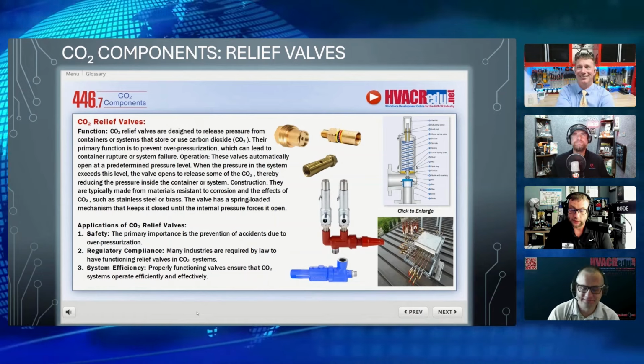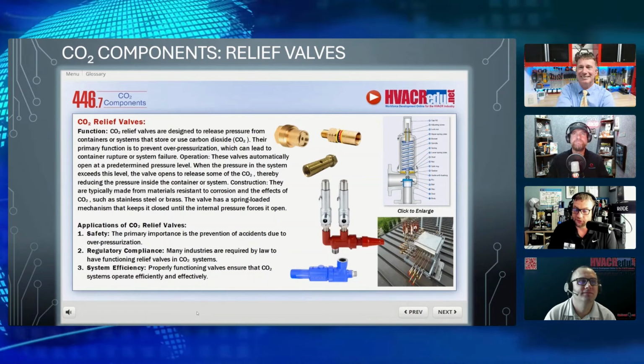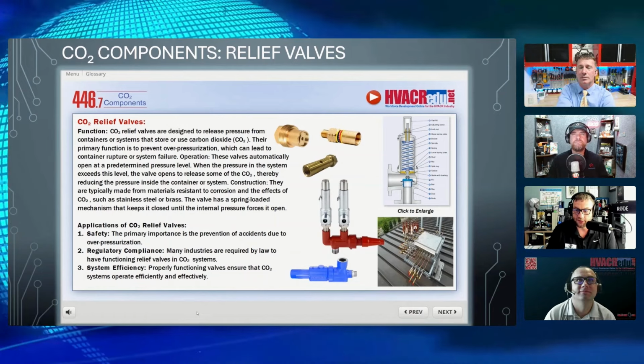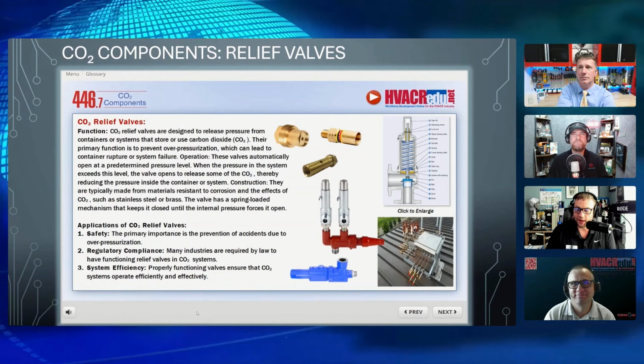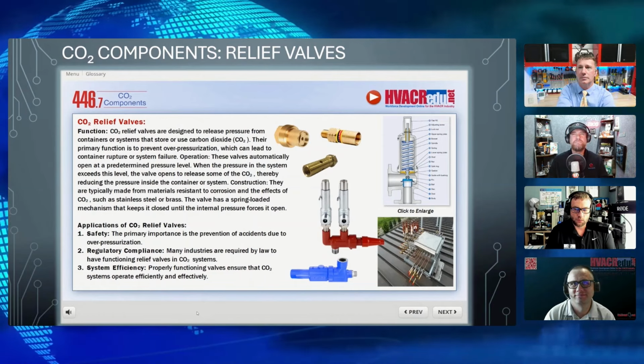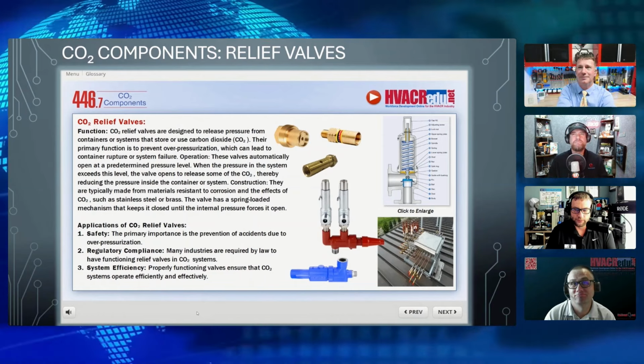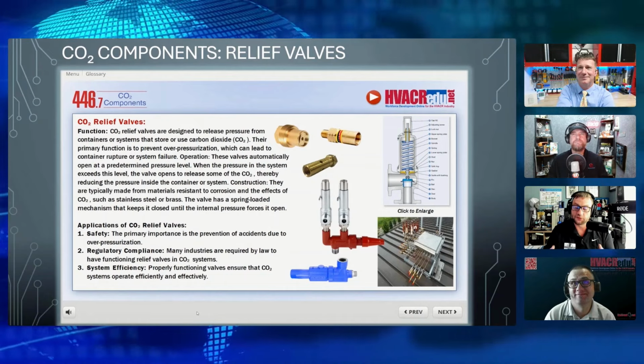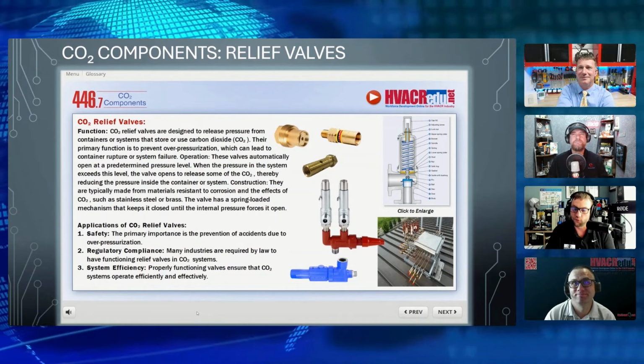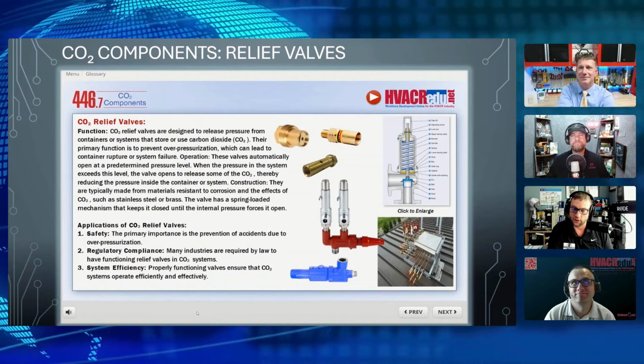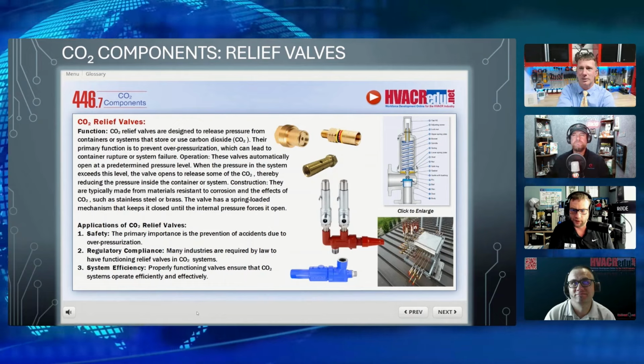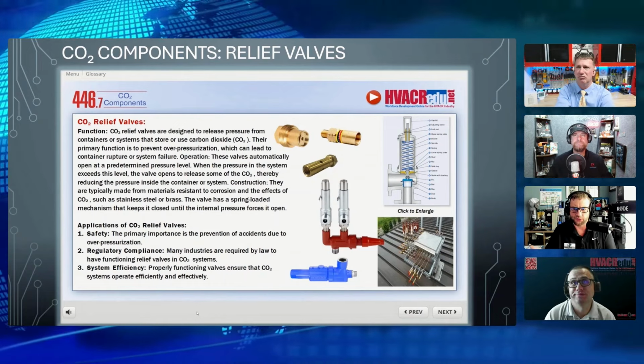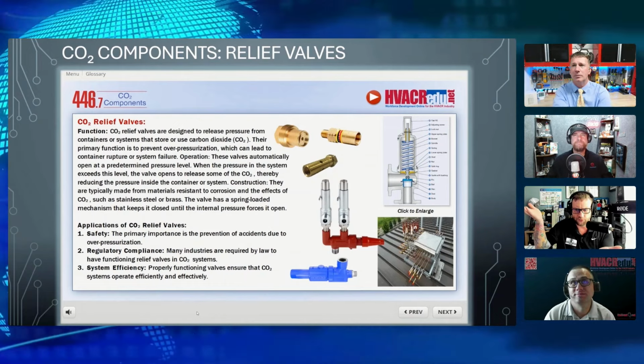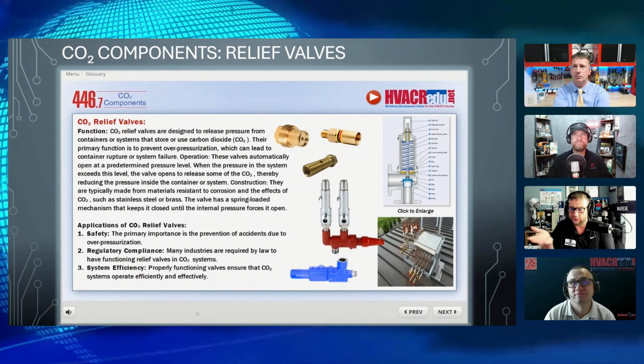Oh, yeah. Actually, a buddy of mine was starting up a system and he called me up. He's like, yeah, yesterday was gasket day. I'm like, really? What happened? He's like, wrong relief on the low temp. Those compressors use something comparable to a 410A compressor on the subcritical side, right? Think about it. About the same pressures, right? Yeah, 200 pounds, 400 pounds. That's really not crazy different.